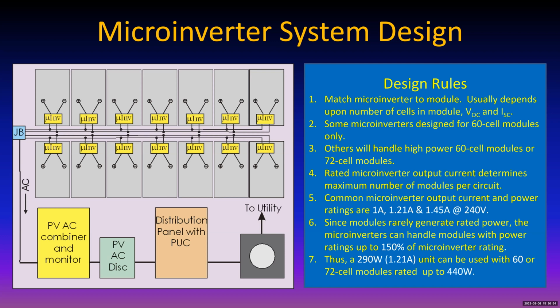Some are designed for 60 cell modules only, and others work fine on 60 or 72 cell modules. Typical module cell counts are 60, 72, and 96. Now you say, well, what about the 144? Well, the 144 cell is really 144 half cells, and the module is really two modules connected in parallel within the same enclosure, so that it performs like a 72 cell module, but more efficiently because of the 144 half cells. And again, I'd love to talk all day about that kind of stuff, but we won't get very many designs done if we do that, but it's really fascinating. So 60, 72, and 96.